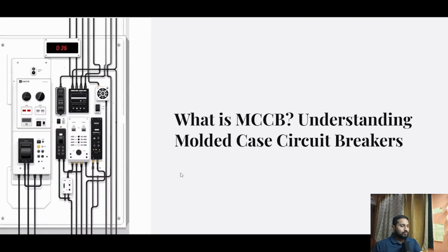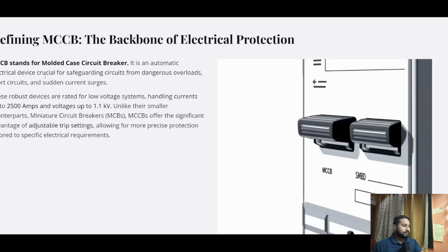So today we are going to see what is MCCB and understand its working and the selection process of MCCB. So MCCB stands for molded case circuit breaker. Here, it's an automatic electrical device that is crucial for safeguarding circuits from dangerous overloads, short circuit, and sudden current surges. Then these MCCBs can handle currents up to 2500 amperes and voltages up to 1.1 kV. So they have more current handling capacity and voltage handling capacity than our traditional counterparts such as miniature circuit breakers and other circuit breakers. So MCCBs offer a significant advantage of adjustable trip settings, allowing for more precise protection which is tailored to specific electrical requirements.